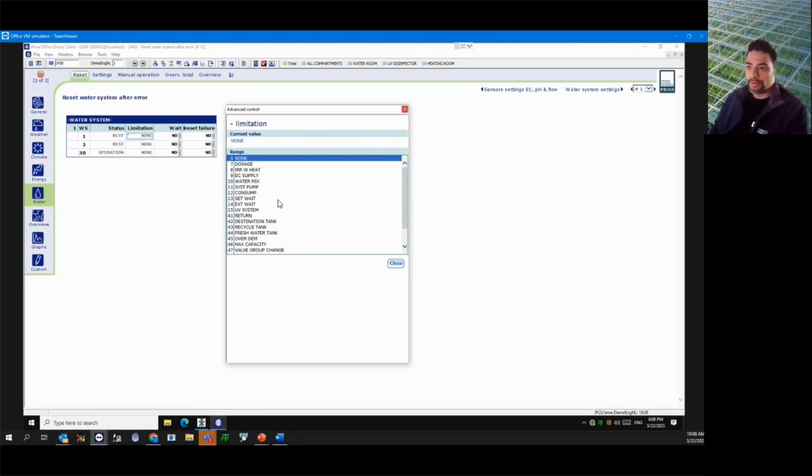So if you have a Priva water system, depending on which one you have, say you have a NutriFlex with a mixing tank, there is a certain number of protections that we have to stop the pump from running if certain things happen, right? So the first thing is if the mixing tank runs empty. Then there's an overload protection for the motor, if that gets tripped, or if there's a high temperature switch on the pump. So those 3 things are essentially connected all together, and they will send a signal to Priva, and we will interpret that as an external wait. That is not a software or controls thing. That's an actual physical thing that happened, right?